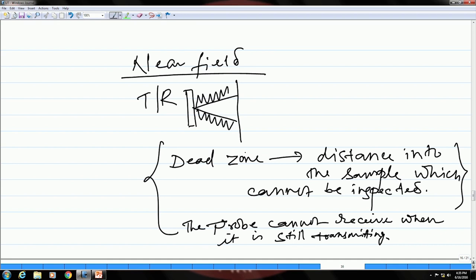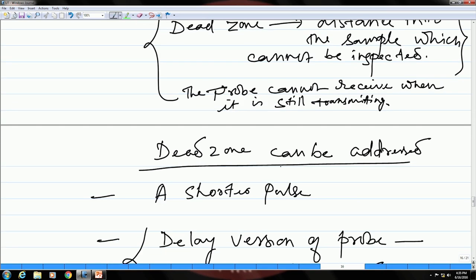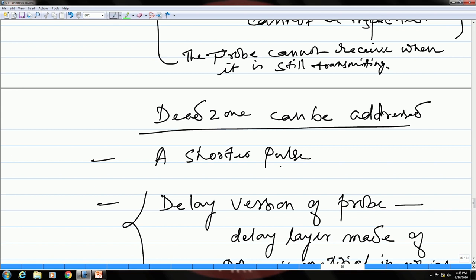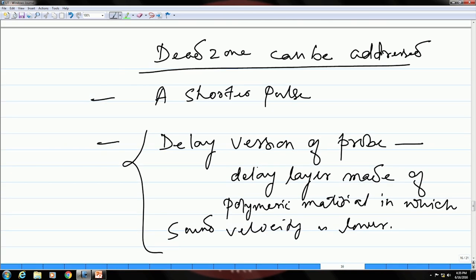We saw how the dead zone can be addressed. There are different ways by which the dead zone effect can be addressed. One is using a shorter pulse or high frequency pulses. The second method is a delay layer, which will delay the echoes coming back to the probe, giving enough time for the fluctuations to die down completely so the probe will be ready to receive.